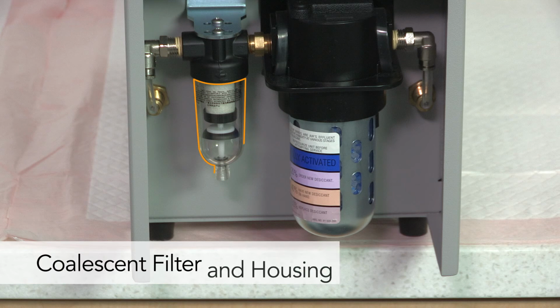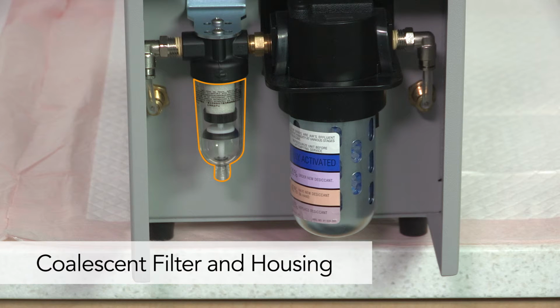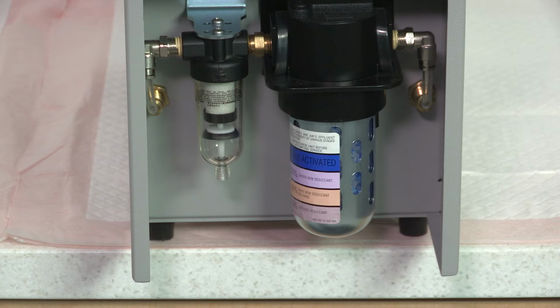Before pressurizing the endoscope, the incoming air must be filtered through the coalescent filter. This filtration system removes oil and air particulates and ensures that only filtered air enters the endoscope.